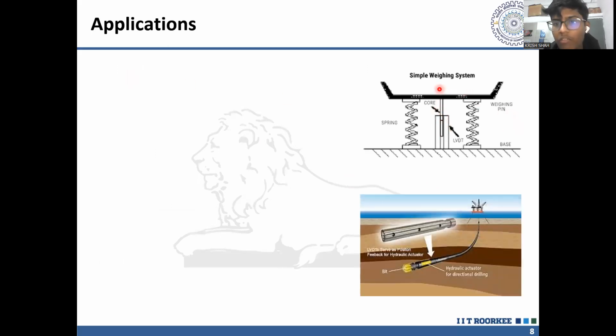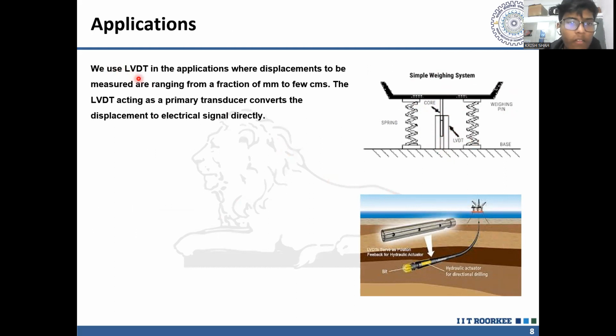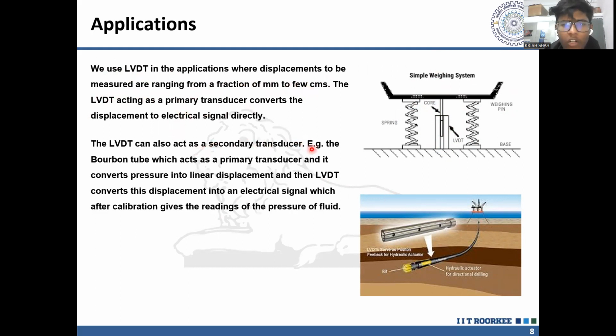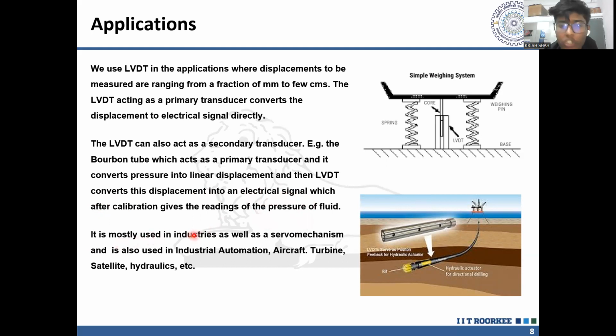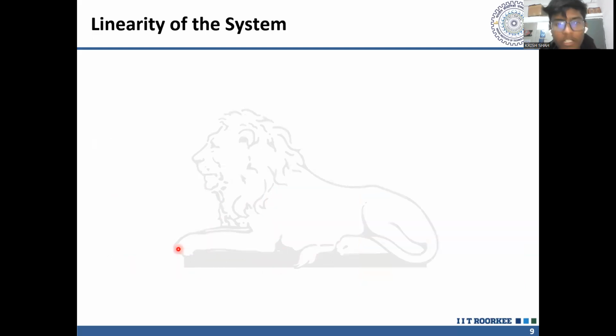In applications, here we can measure the weight of a system. The movement of the LVDT here will give us the displacement, as this is the secondary transducer and this is the primary. Both are converted into a displacement of the LVDT core, and thus we can measure it. LVDT is used to measure displacement ranging from a fraction of a millimeter to a few centimeters. LVDT can also act as a secondary transducer, as earlier mentioned, and it converts to an electrical signal. It is mostly used in industries as well as servo mechanisms, and it is also used in industrial automation, aircraft, turbines, satellites, hydraulics, and many other places.